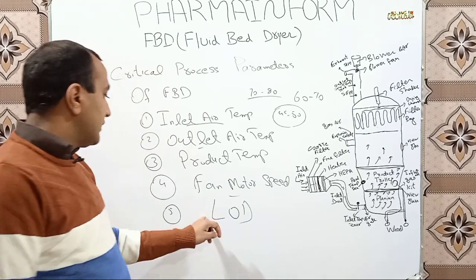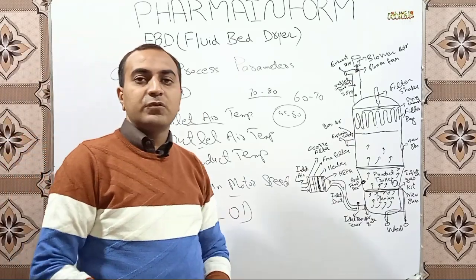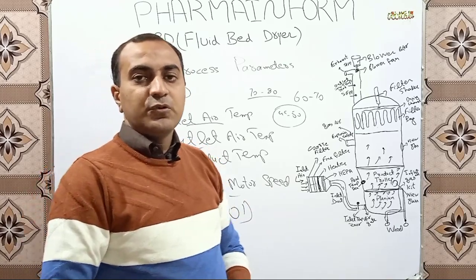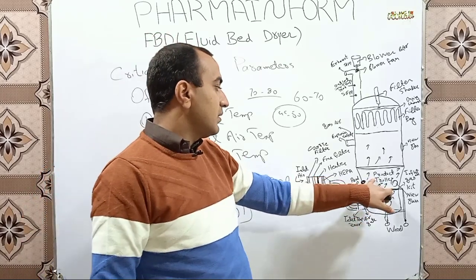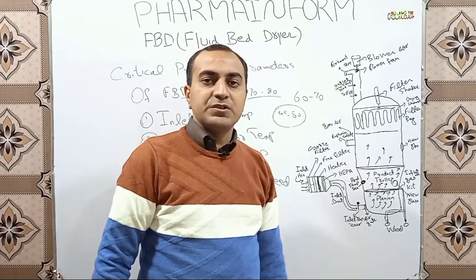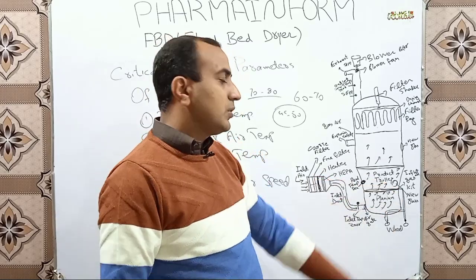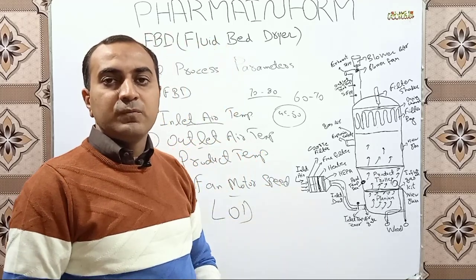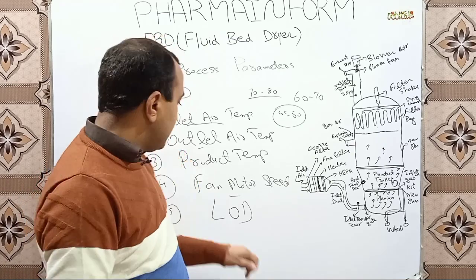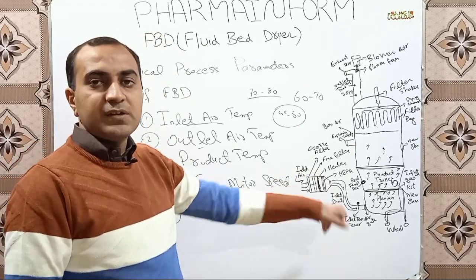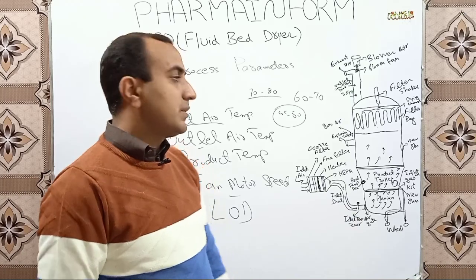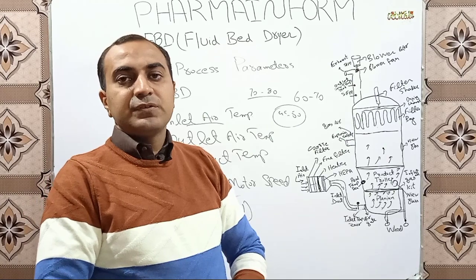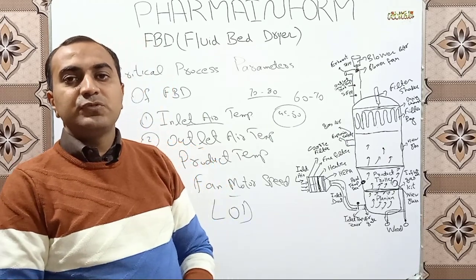The last parameter is LOD, or loss on drying. The completion of the drying cycle depends on the loss on drying. From the sample collection port attached to the product trolley, we take a sample at specific intervals and perform LOD testing on a moisture analyzer. When the LOD comes within the required range, we can confirm that our product is dried. These are the most critical process parameters for products dried using a fluid bed dryer.